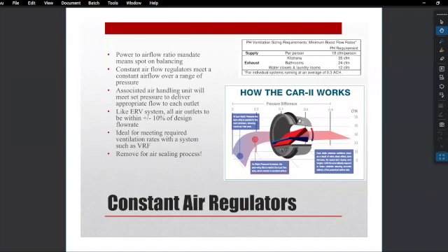And one more important thing in meeting those flow rates is using these constant air regulators. With a manual damper, you're making adjustments, and it's a lot of work to make manual adjustments everywhere and go back and forth to try to make the flow rates be within 10% of your design flow. And then you also have to prove this to commissioning. The CAR damper is great because it acts within a prescribed range and meets a set flow. They even have CAR dampers now where you can tighten or loosen the baffle in it to permit or restrict airflow. So even if your CAR damper isn't providing the right airflow rate, you can still make minor adjustments to get it to deliver the right CFM.